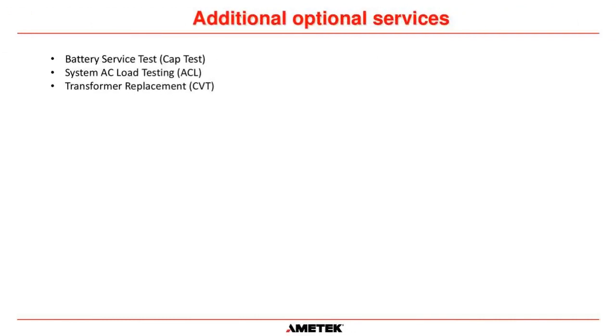And we do offer optional services. We have the ability to do battery capacity tests, system AC load testing. Many customers ask for that, especially after a PM10, because you are replacing so many components within the UPS. A lot of clients like to have the UPS tested before they put it back on plant load. So we have a wide variety of AC load banks that we can send out and test the UPS before we put it back online. It's a very common additional service that some of our customers want. And we also do transformer replacements, the CVTs, the constant voltage transformers, which are installed in our Ferroresonant and our old analog UPSs. Okay.